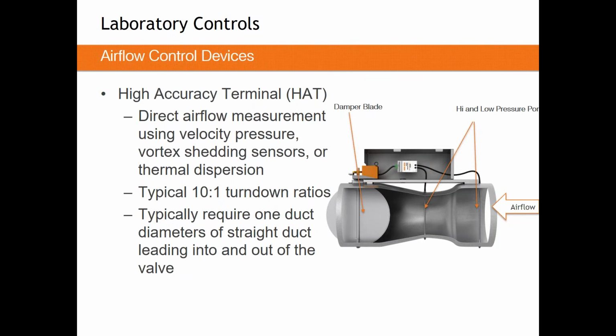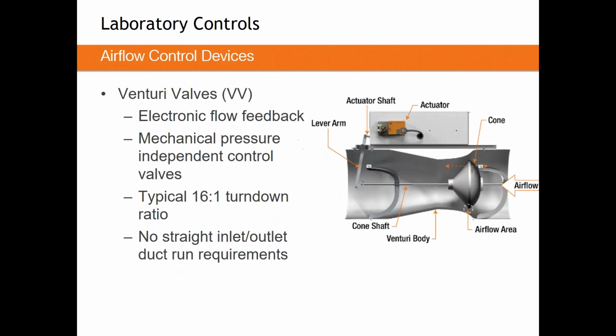That brings us to the slightly more complicated unit in the Venturi valve. Now, the VV style device is a complete shift in mindset when measuring and metering airflow. The first thing to remember about a Venturi valve is it does not measure airflow, not in any way, shape, or form. It doesn't measure flow. There are pressure taps on a Venturi valve. You may be able to see them just in the top end of that valve, poking into the valve there.